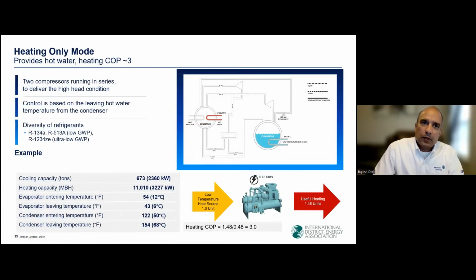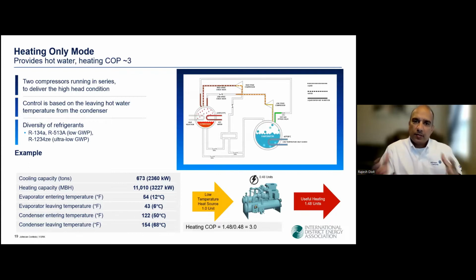Now we are going on to our last mode, which is the heating only mode. I won't explain this mode in detail because this mode is actually very similar to the simultaneous cooling and heating mode animation that we showed you previously. There is only one difference, which is in the evaporator section. Whatever is passing through the evaporator tube bundles is referred to as the low temperature heat source and not chill water. So it is something other than chill water. What can that something else be?